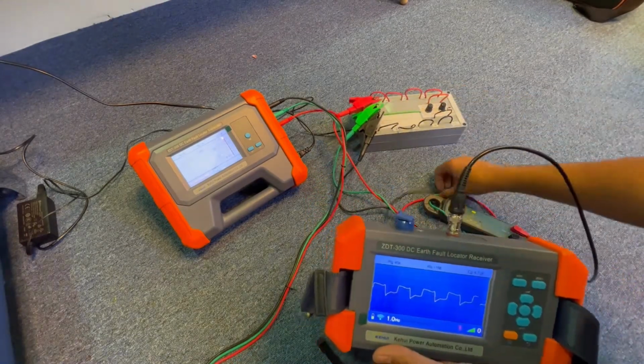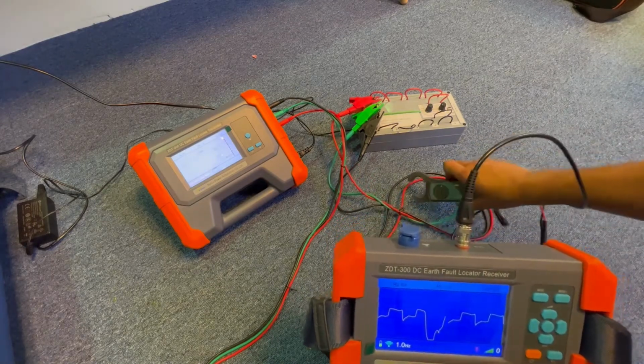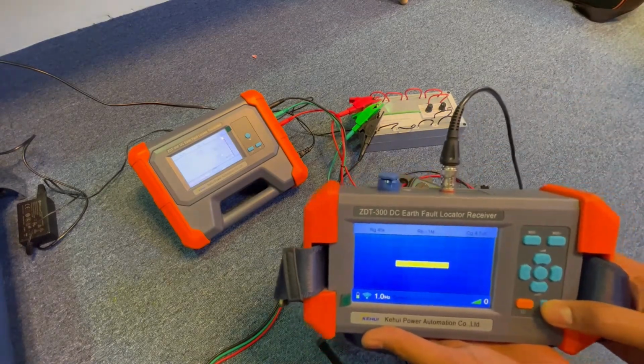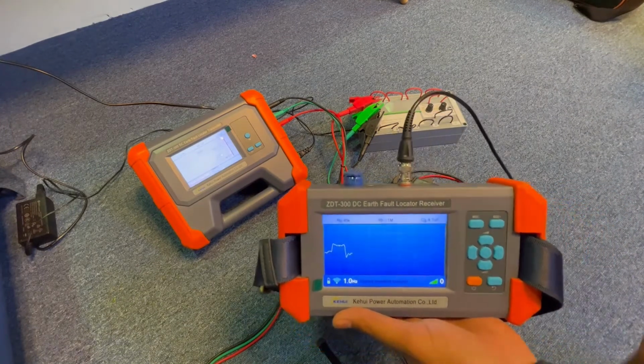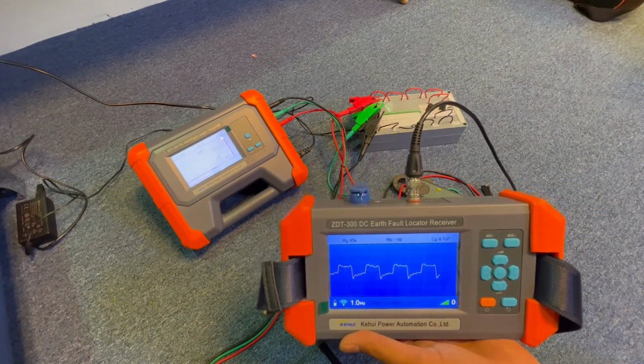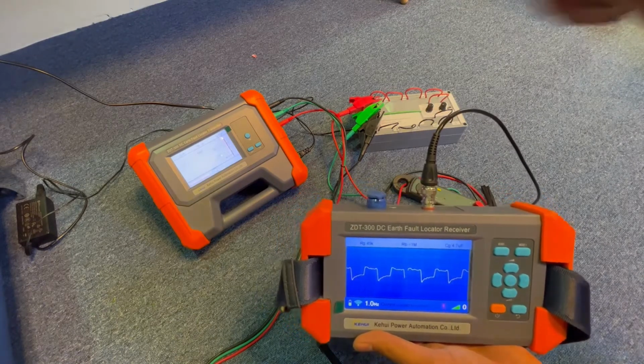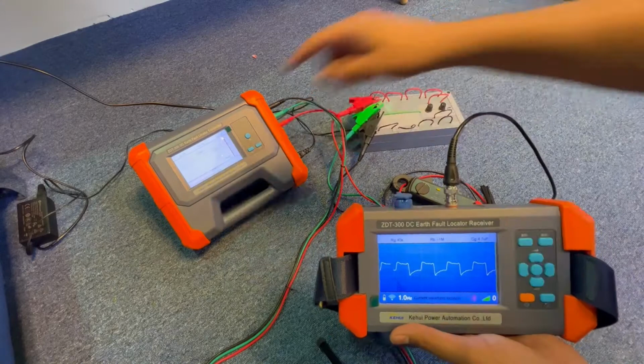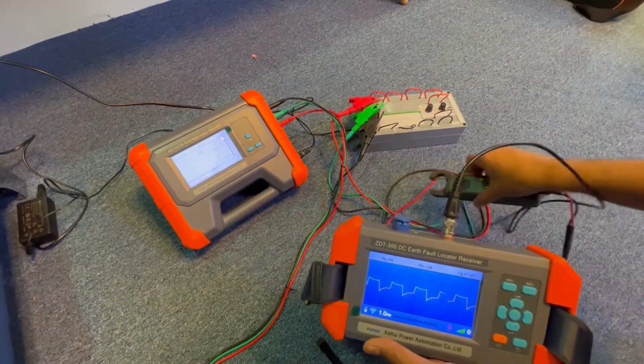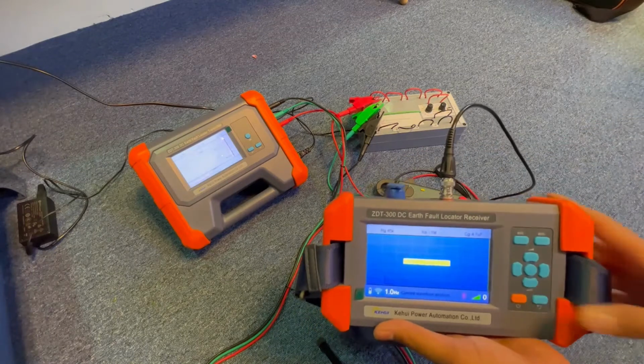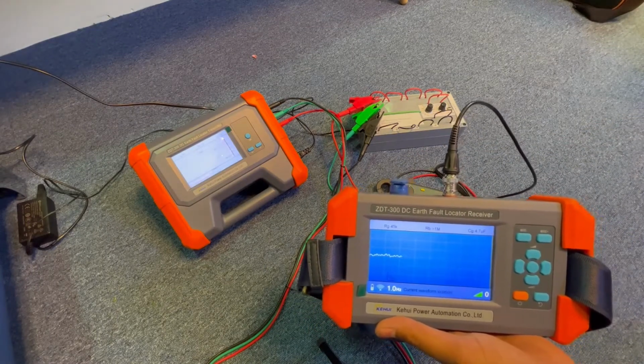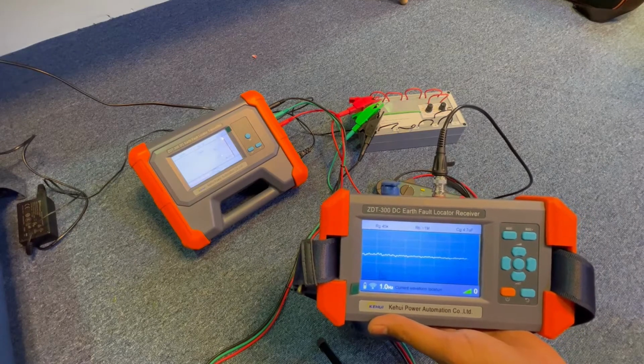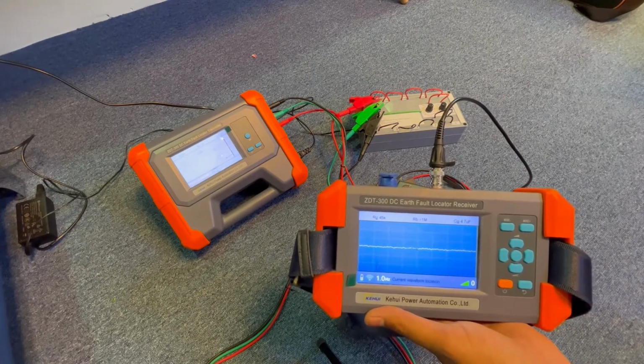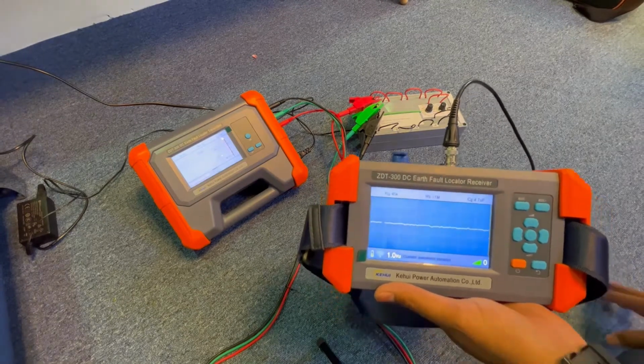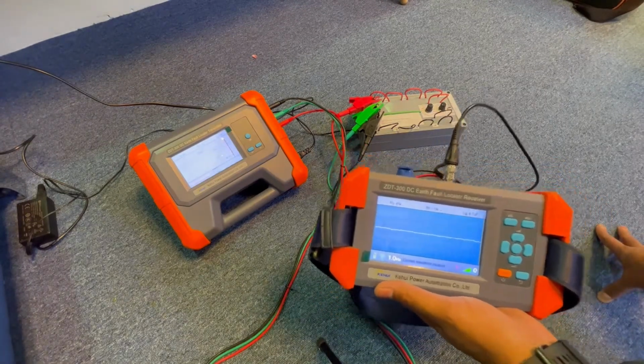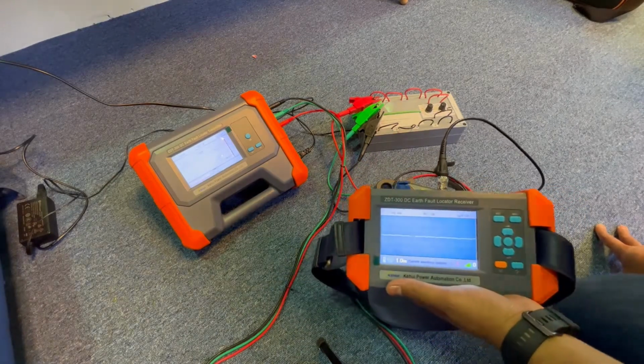So now let's connect to the positive feeder and then refresh. You can see that the positive feeder is grounded. We can see from the transmitter as well, it shows positive busbar ground. So it's very clear. Let's go to the negative, connect to the negative, then refresh. You can see that there is no fault in the negative, which means that there is no waveform. So now let's start with the feeders. Let's connect the feeders one by one and see which feeder is faulty.